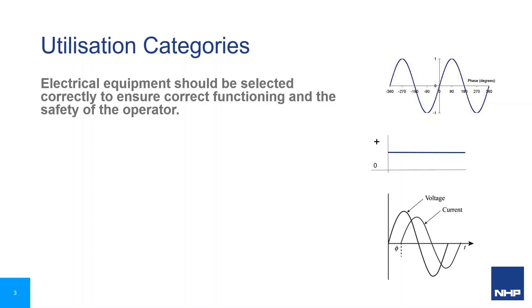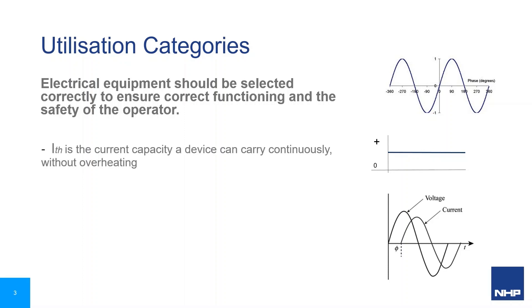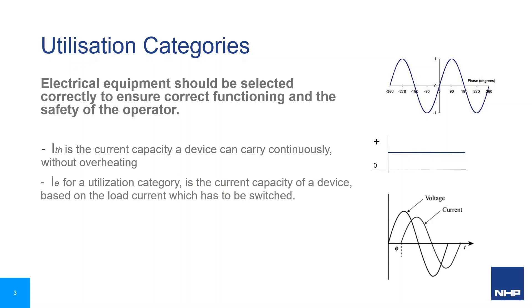The selection of a device suitable to fulfil the required switching functions is based on the characteristics of the load. The most common current rating for a device is ITH, which is a thermal rating for its capacity to carry a constant current value for an extended period of time without overheating. However, the loading of contacts by current and voltage when circuits are made and broken during switching is critical, with the making and breaking current for a resistive load significantly different to those of an induction motor. So utilisation categories are used.